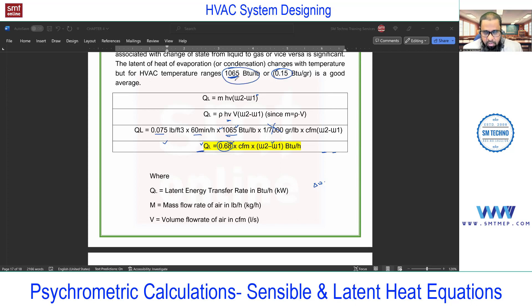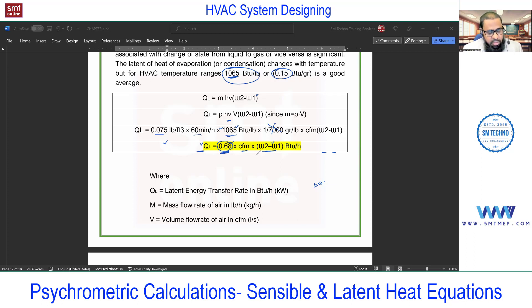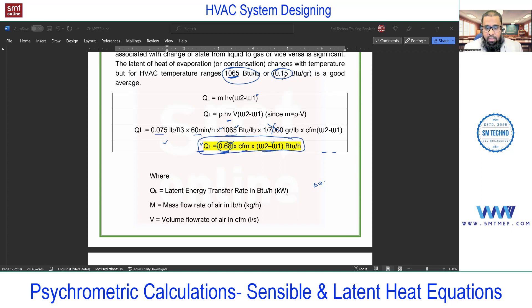So 0.68 is a factor based on the density of air, latent heat of evaporation, and unit conversions. The final latent heat equation is: Ql = 0.68 × CFM × Δw, where Δw is the change in humidity ratio in grains per pound. This applies for total air, fresh air, or infiltration air as per the case. For sensible we use delta T — dry bulb temperature difference — and for latent we use delta w, the humidity ratio change. Importantly, 0.68 is consistent across all handbooks — unlike sensible where you find 1.08 or 1.1, this value is fixed.